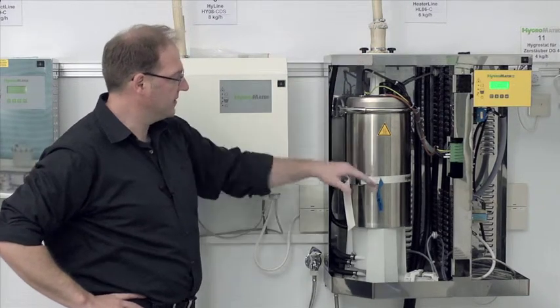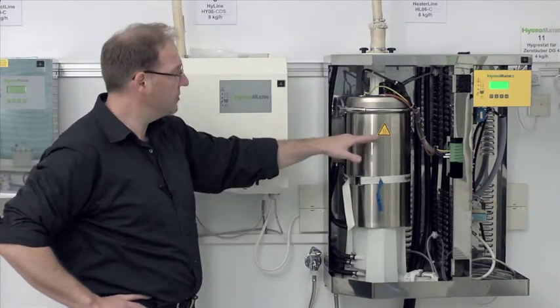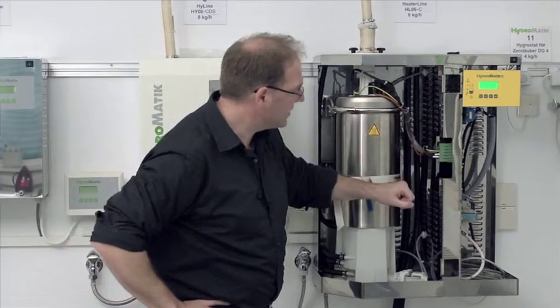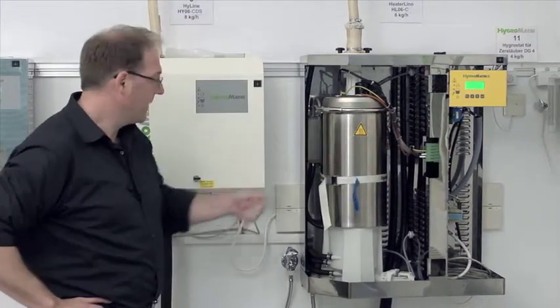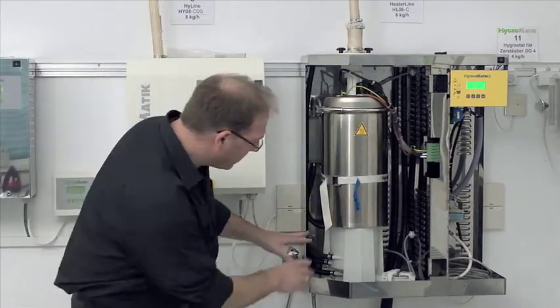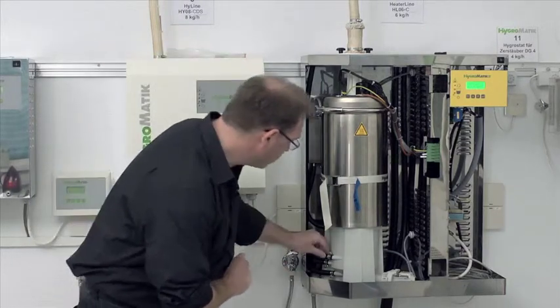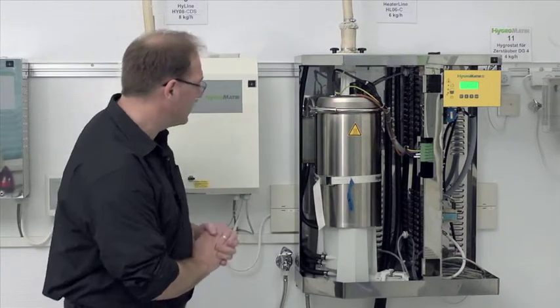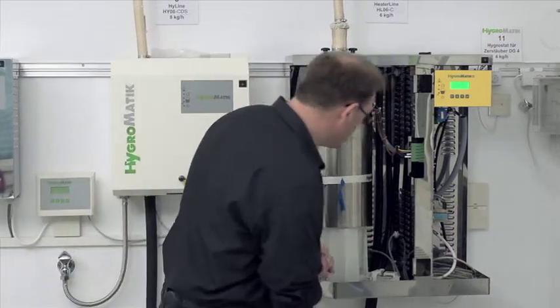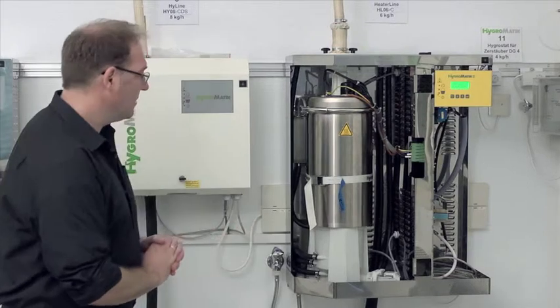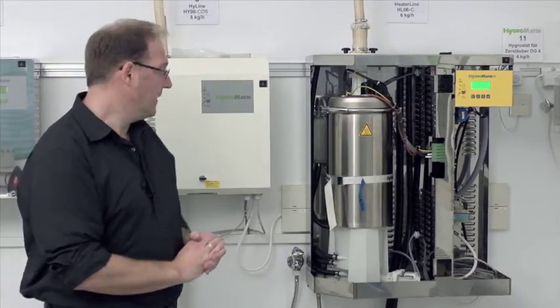Yes, and now I have waited five to ten minutes. The unit has filled itself with water. We have a request for the unit. It is now producing steam. I monitor during this time if somewhere there is leakage in the lower area. Check the hoses. Check the O-rings I have replaced. But it all looks quite okay so far. The unit can operate like this.